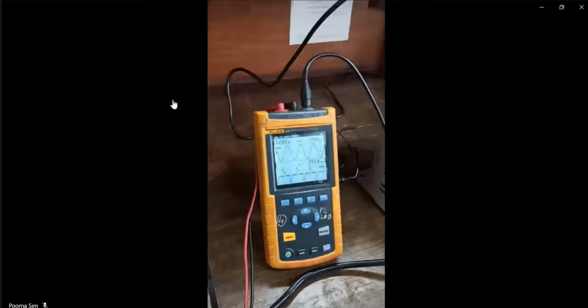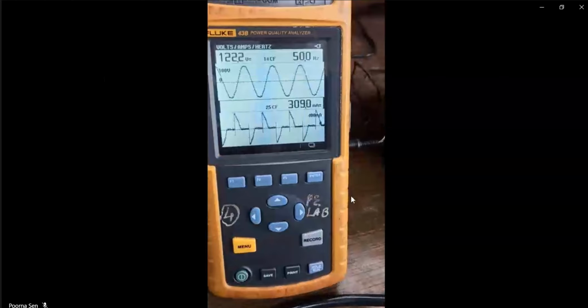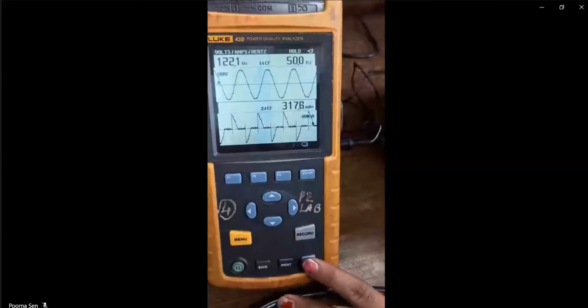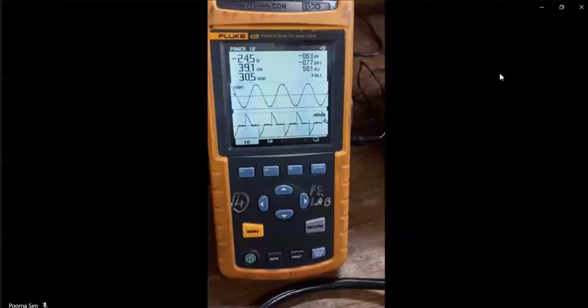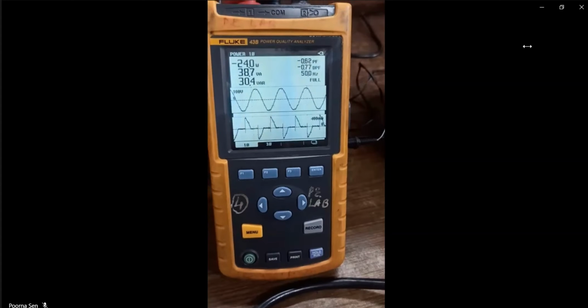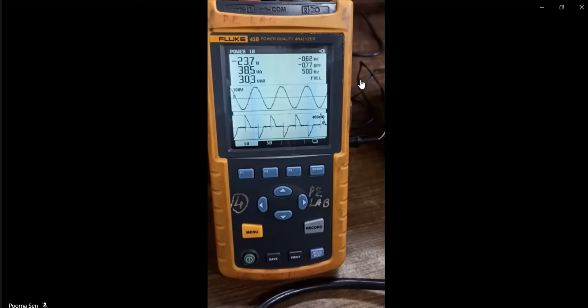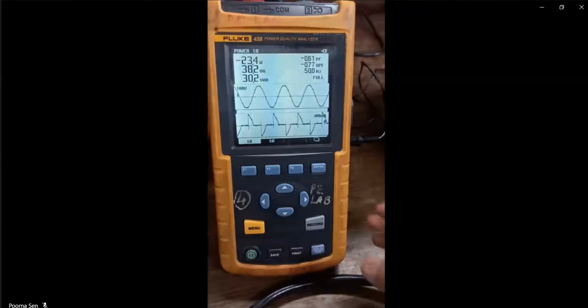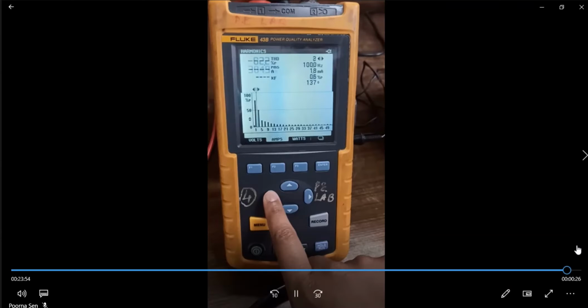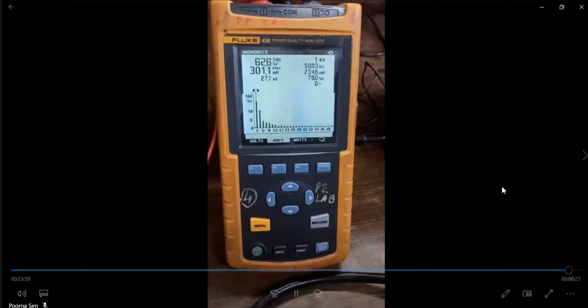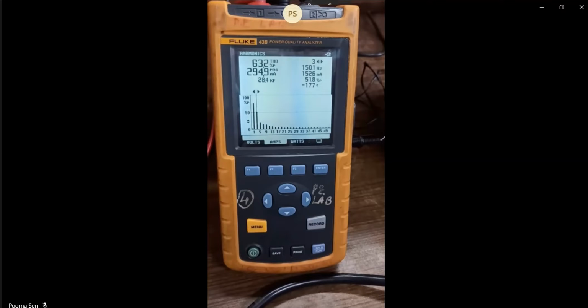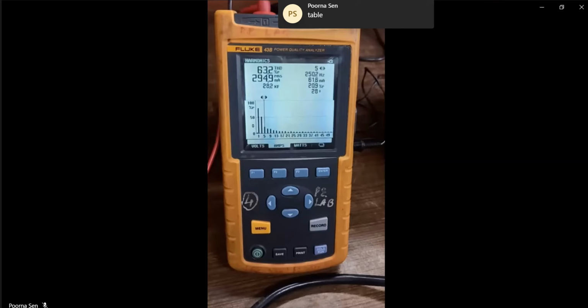Now we will set a firing angle to 6.2 milliseconds. Input current is 317 milliampere. Power is 24.5 watt. Reactive power is 38.8 volt ampere. Power factor is 0.62. DPF is 0.77. THD is 62.4%. First harmonic is 230 milliampere. Third harmonic is 152 milliampere. Fifth harmonic is 61.6 milliampere. And seventh harmonic is 45.3 milliampere.